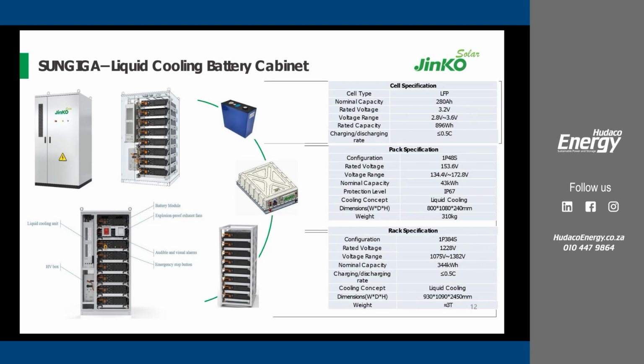With this cooling unit, there are actually cooling ducts to ensure direct flow of cooling from the master cooling units to each of the battery pack cooling plates. Ideally, the highest temperature point and the lowest temperature point in these small cabinets is less than 2 degrees apart, so we're able to ensure very good round trip efficiency, up to 94%.